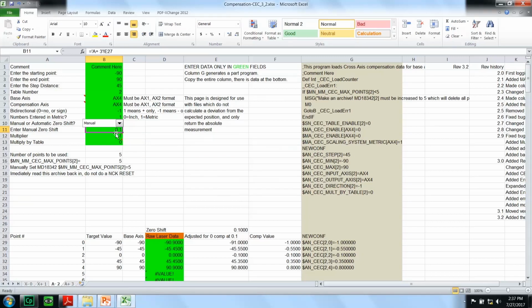Again, I'm going to remind you that the reason this shows up as an effect so often on the rotary axes is because we set rotary axis 0 with the test bar and indicators. When we set up a rotary laser, we usually drive to the negative end of travel, or negative soft limit, somewhere near there. We zero the laser out there. We move all the way through the range of motion. We typically pick up a value at axis 0. If we don't shift and correct that properly, we've moved the position that we used with the test bar.